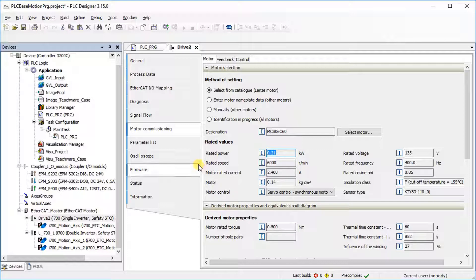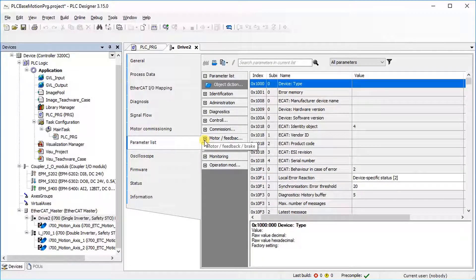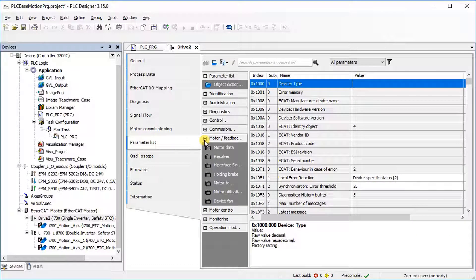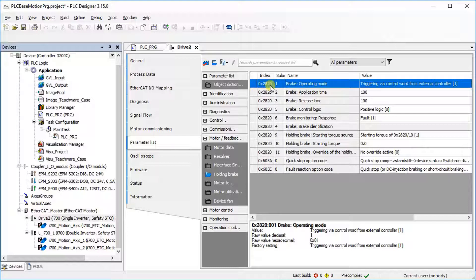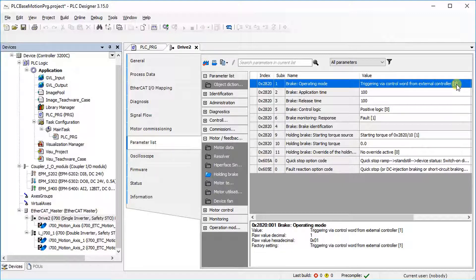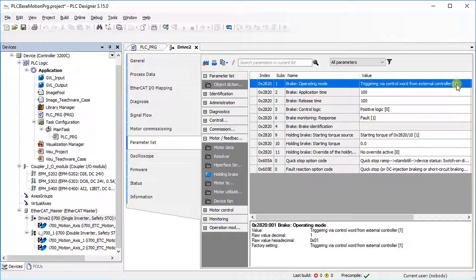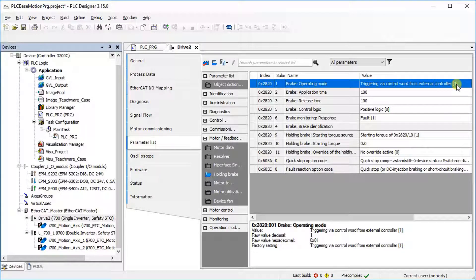Go to the Parameter List tab and then select Holding Brake under the Motor or Feedback or Brake tab. By default, the value of the Brake Operating Mode parameter is 1, meaning the brake logic functionality within the controller application. In this mode, brake control is processed by the controller via control word. This mode provides torque pre-control, which prevents active loads from sagging, like in hoist applications. It considers the delay time of the holding brake during the opening and closing process via controller application.